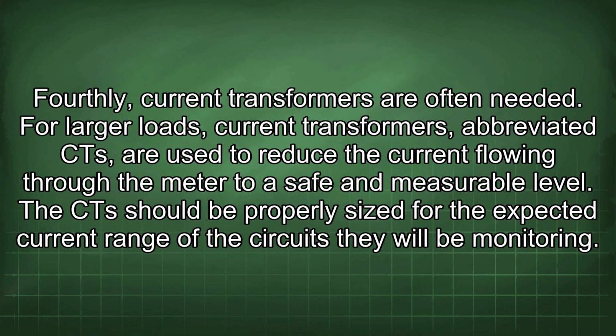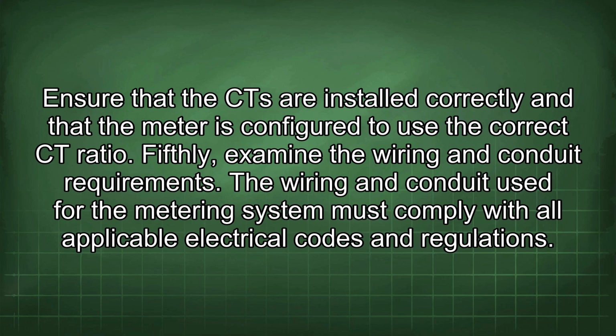Fourthly, current transformers are often needed. For larger loads, current transformers, abbreviated CT, are used to reduce the current flowing through the meter to a safe and measurable level. The CT should be properly sized for the expected current range of the circuits they will be monitoring. Ensure that the CTs are installed correctly and that the meter is configured to use the correct CT ratio.